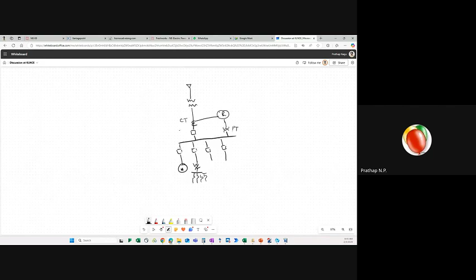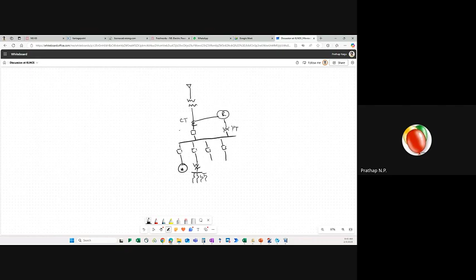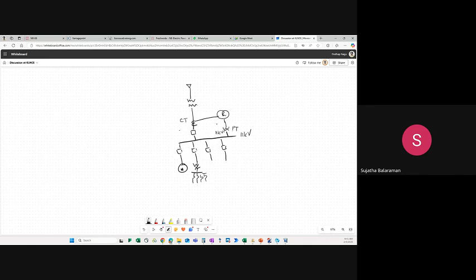But this relay itself needs power to operate, right? It cannot power from this way. It could power from the PT. That's one idea. Instead of just getting the voltage information, it could actually power itself, because this is, let's say, this 11 kV bus, but this PT will take it down from 11 kV to what's the secondary of a PT in India? Can anybody tell me? It's a standard. What's the secondary voltage, I'm sorry, of a PT, potential transformer?